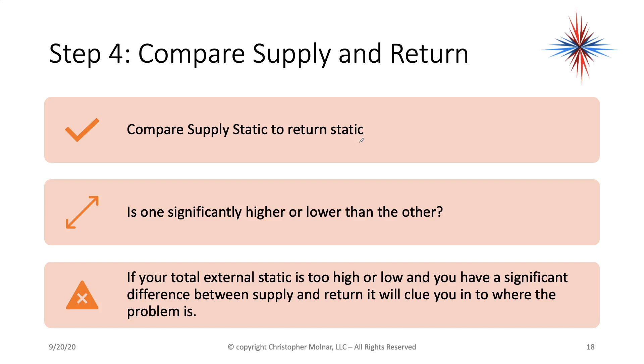Then we compare the supply and return individually. My return was 0.46 and my supply was 0.16. Is one significantly higher than the other? Yes, it is. My return static at 0.46 is significantly higher than the supply at 0.16. Then we can go and find out what part of our problem is — that's the side you want to concentrate on first.